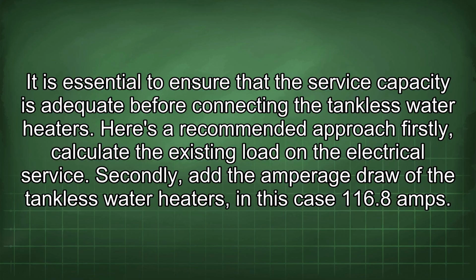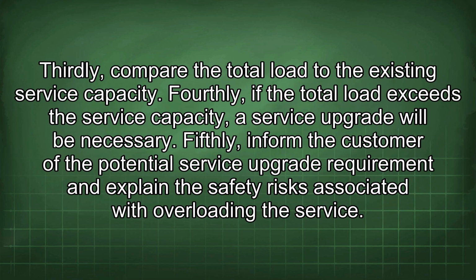Here's a recommended approach. Firstly, calculate the existing load on the electrical service. Secondly, add the amperage draw of the tankless water heaters, in this case 116.8 amps. Thirdly, compare the total load to the existing service capacity. Fourthly, if the total load exceeds the service capacity, a service upgrade will be necessary.